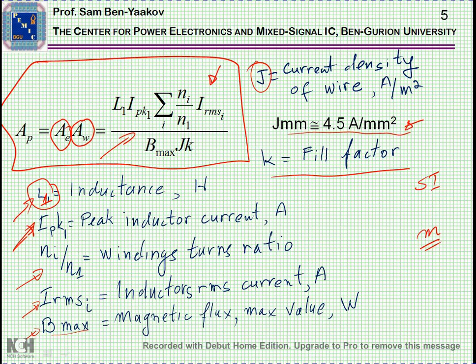And then there is the fill factor, which stands for the fact that when you are winding into the winding area, there are some voids here. Here's the winding inside the core. And consequently, you cannot utilize all the area. You can improve if you'll have a square wire, but for round wires, and even for square wires, K will always be smaller than 1. A reasonable number is 0.7, depending on the method of winding, what type of machine you are using, or maybe it's hand winding.